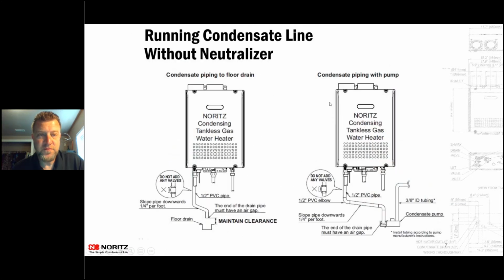All righty. So with condensing units, they are going to condensate. So there is condensate that is going to be coming out of any condensing unit. On the bottom of every condensing unit that's on the market right now, there is a condensate drain. Usually they have a trap that is built into the unit itself. So if you are running that condensate down to the floor drain, you're not going to want to put a trap on the outside of the unit, because every one that I've ever seen has a trap on the inside of that unit.